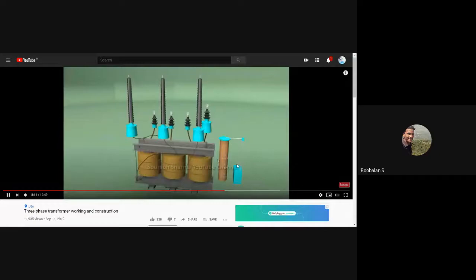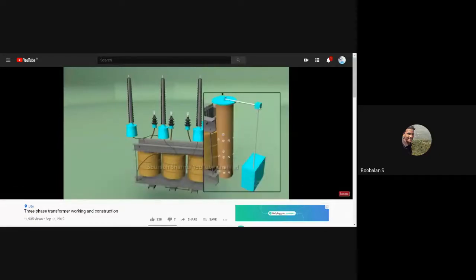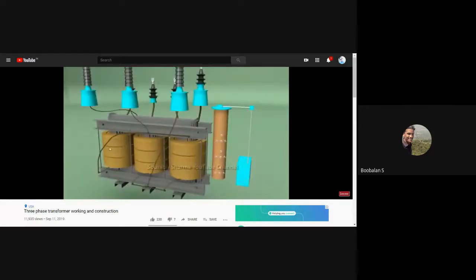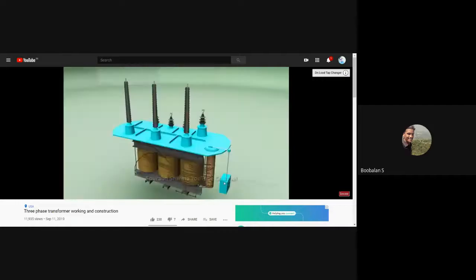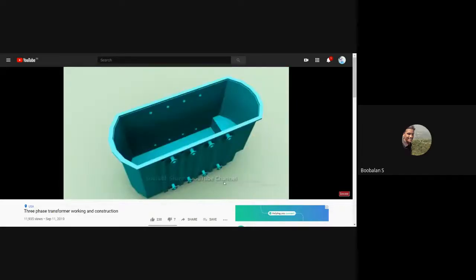The transformer assembly is inside the tank, and it is controlled through a motor which is installed inside a panel, and the panel is fixed outside the transformer. The connection we have seen so far is explained in a simple way, but in actual the connection of the high voltage winding also includes the tap changer, as we can see here. Now to understand in detail how the connection through the tap changer is made, you can watch a dedicated video on that through this link. Finally, after connecting the tap changer, this complete assembly is immersed in a transformer tank.